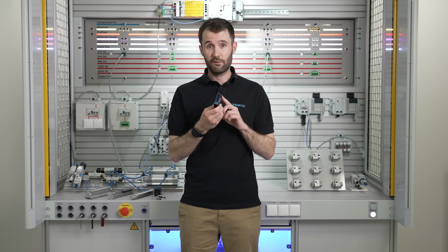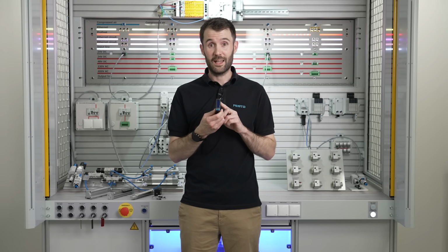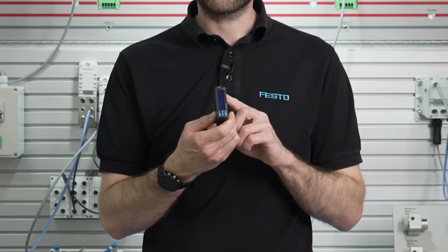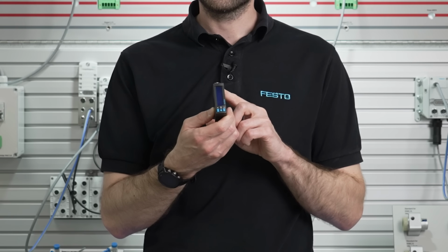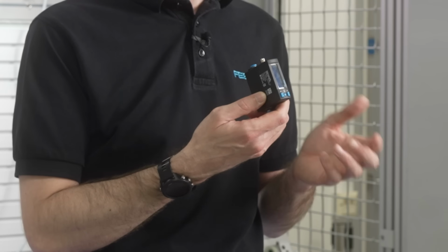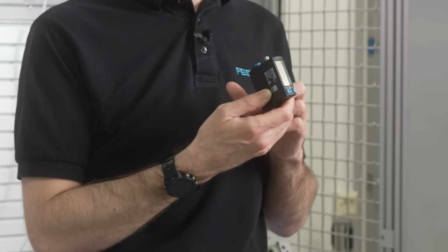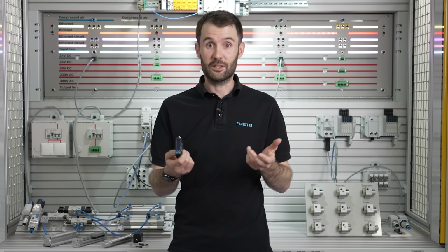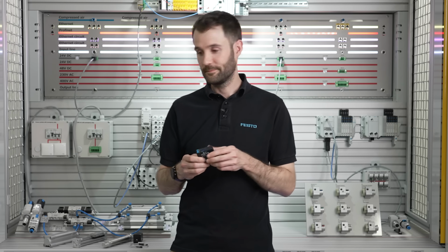We could utilise flow sensors. Flow sensors can also be used to measure the actual air consumption. So then we can look at leak rates and detect if we've got a leak in the system, as we said about that pneumatic cylinder at the start, the failure at the front nose seal, and monitor our overall air consumption, which is our energy consumption of the platform.